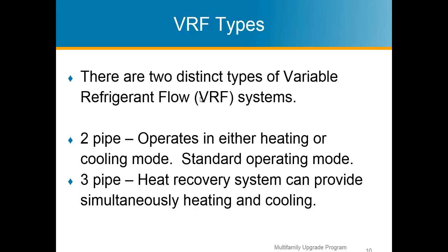All right, so there are two distinct types of VRF systems. There's a two-pipe and a three-pipe. Now the two-pipe operates in either heating or cooling mode, standard operating mode. So that's very similar to your standard unit. It can either be in heating or in cooling.